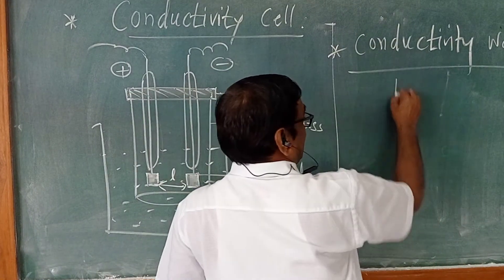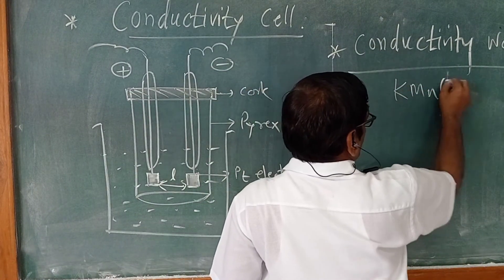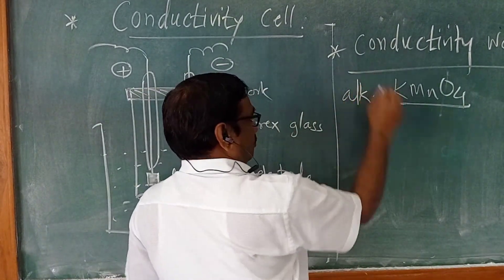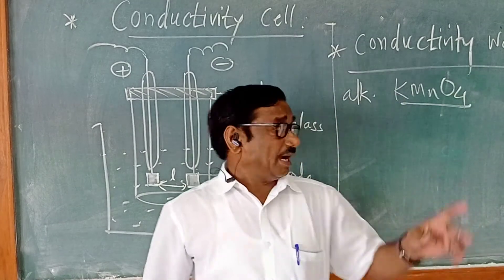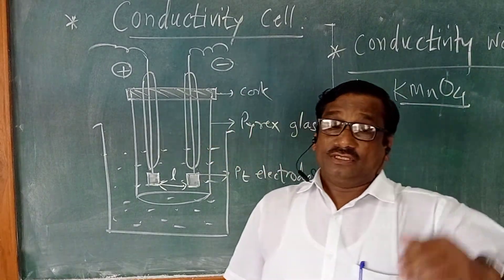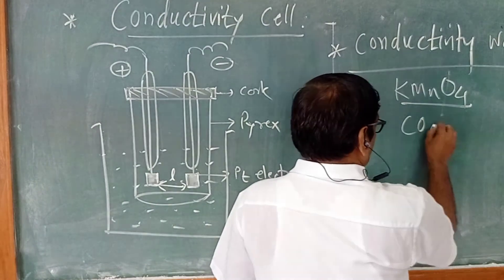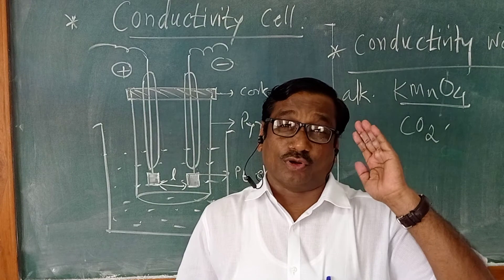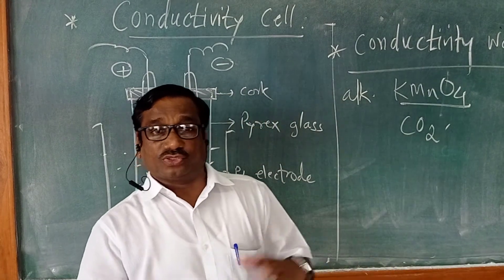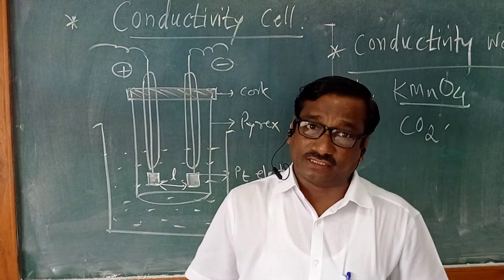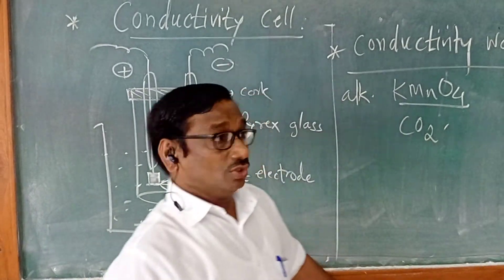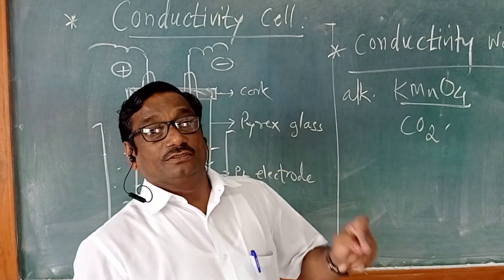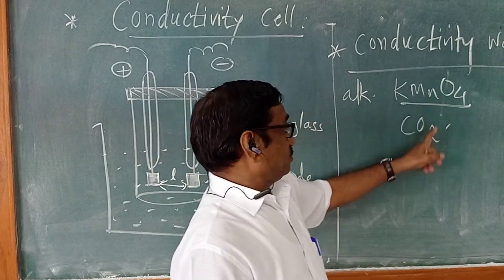The distilled water is redistilled by adding alkaline KMnO₄. Why? Because in distilled water, if carbon dioxide (CO₂) is present, it forms carbonic acid. That carbonic acid dissociates into H⁺ and HCO₃⁻ ions, which induce unwanted conductance. So distilled water is redistilled by adding alkaline KMnO₄, which causes the CO₂ to be expelled.